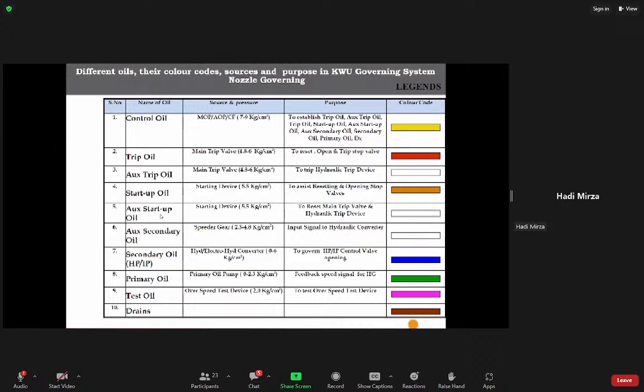These are some different oils covered in the governing system. Most of you know about these governing system oils. What are the oils used in this governing system? One is control oil, trip oil, auxiliary trip oil, startup oil, auxiliary startup oil. Don't go by this; there is some graphical mistake here. This is basically white and red here, and here auxiliary startup will be orange and white, and auxiliary secondary oil will be white and blue. The types of oils we have studied are: control oil, trip oil, auxiliary trip, startup oil, auxiliary startup, auxiliary secondary oil, primary oil, test oil, and drains.